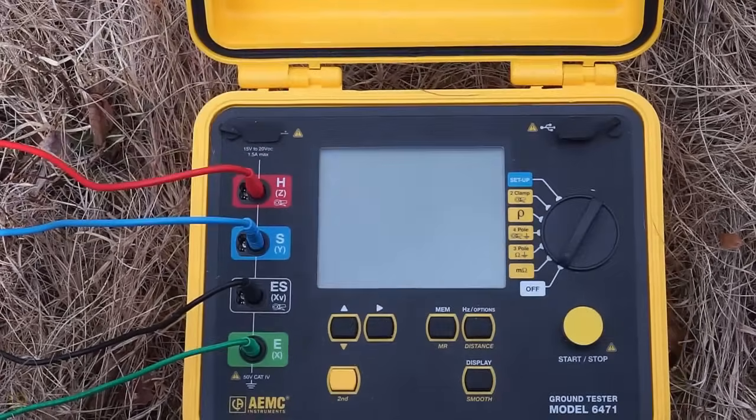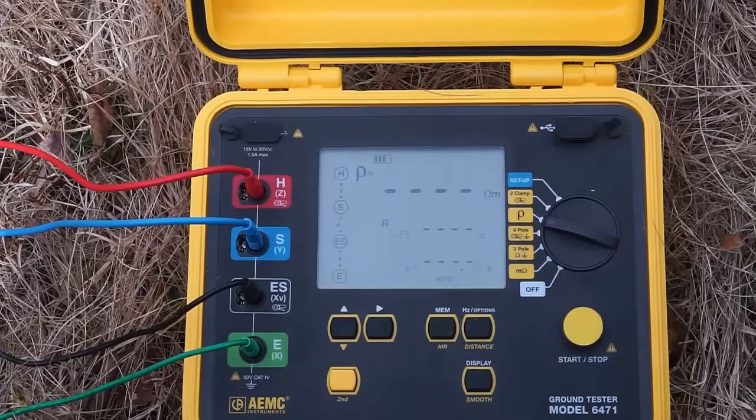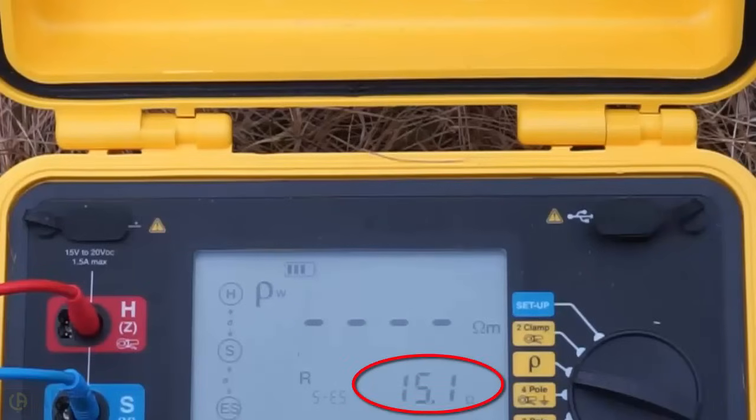If your instrument doesn't offer automatic soil resistivity calculation, simply take a resistance reading. For example, if you don't enter the electrode distance, the rho setting on the Model 6471 displays soil resistance, which is 15.1 ohms. We can now use this value to manually calculate the resistivity of the soil.